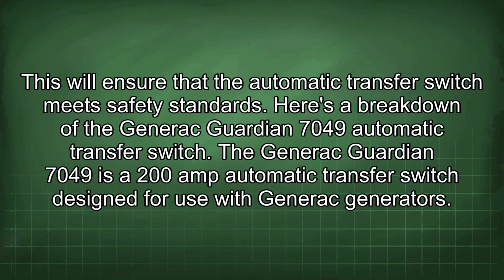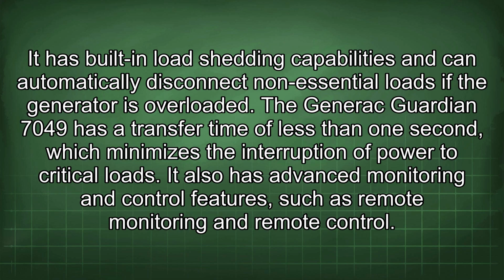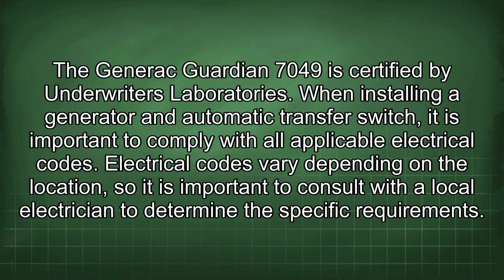Here's a breakdown of the Generac Guardian 7049 automatic transfer switch. The Generac Guardian 7049 is a 200 amp automatic transfer switch designed for use with Generac generators. It has built-in load shedding capabilities and can automatically disconnect non-essential loads if the generator is overloaded. The Generac Guardian 7049 has a transfer time of less than 1 second, which minimizes the interruption of power to critical loads. It also has advanced monitoring and control features, such as remote monitoring and remote control. The Generac Guardian 7049 is certified by Underwriters Laboratories.